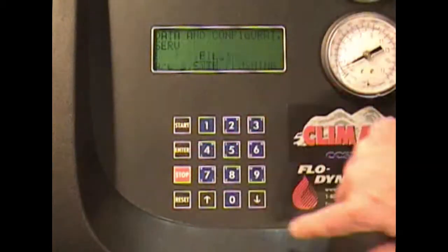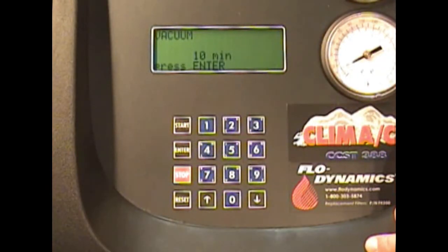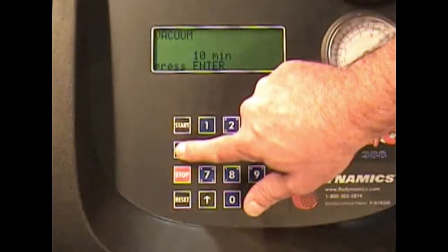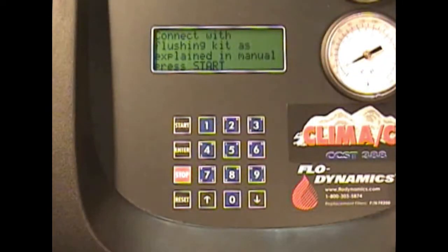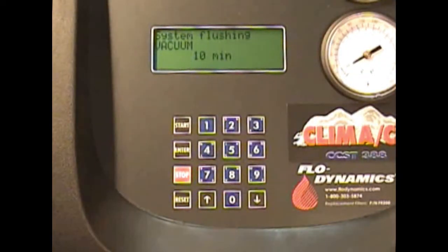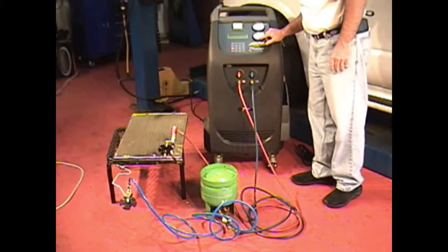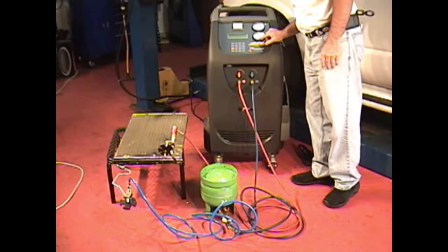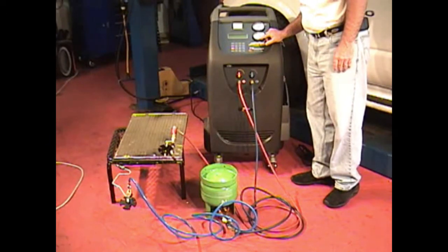Set the vacuum time. The default setting is 10 minutes. During this time, look for difficulty reaching vacuum. This may indicate a connection leak. The CCST388 will then charge 5.5 pounds of R134A into the system or component and recover it from the surge tank. This process will repeat 3 times.